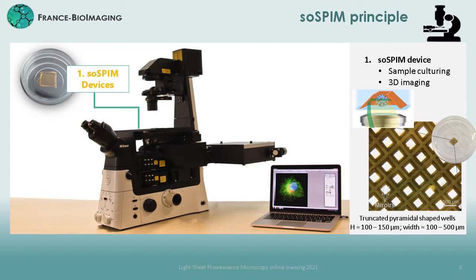A soSPIM system looks like this. It is compatible with any inverted microscope, and therefore benefits from their standard imaging modalities, such as epifluorescence or phase contrast imaging, and it is composed of three main components. The first is microfabricated devices that integrate the 45-degree mirror, allowing to create the excitation light sheet. They are positioned as any standard petri dish on an inverted microscope and allow for 3D sample culture. We developed several designs adapted to different kinds of samples, from single cells to spheroids or organoids.